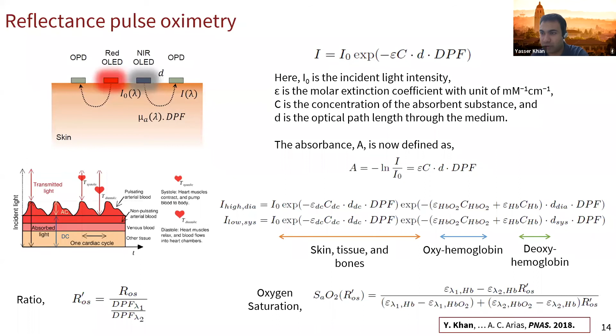And now I'll just briefly show the math and the analytical model that goes behind making a reflection mode oximeter. Essentially, you will have an incident light, and then that goes through exponential decay based on skin, tissue, and bones, and oxy and deoxyhemoglobin. And from here, you can analytically calculate what's the oxygen saturation if you're using two different colors of light. And we showed that the same principle that is standard for transmission mode oximetry applies to reflection mode pulse oximetry also. And once we validated the device and also the model, we went to a reflection mode measurement. Here, it's on the wrist. We are basically doing the same measurement with red and green light. And we were able to produce the same PPG signal and oxygenation.